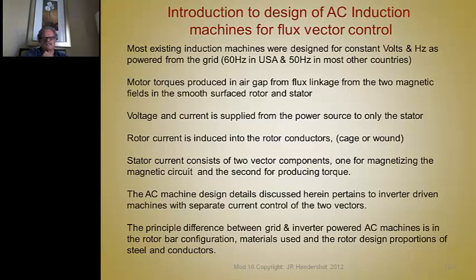the characteristics of how the machine performed at fixed voltage and frequency caused the designers to optimize the rotor configuration, and the stator to some extent, but mostly the rotor configuration, so that it would give the desired performance at a fixed voltage and frequency.